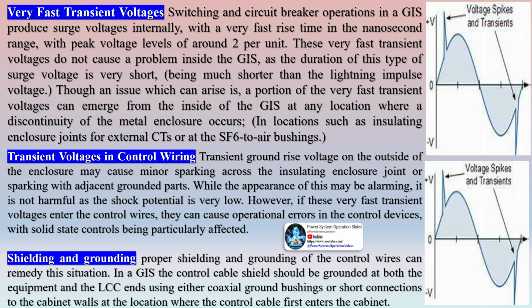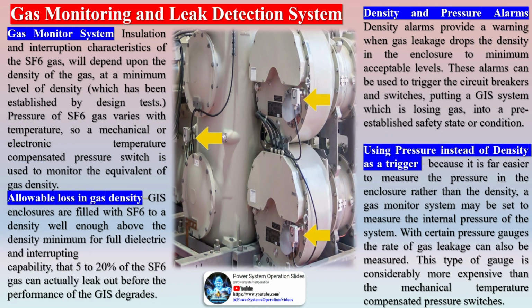These very fast transient voltages do not cause a problem inside the GIS, as the duration of this type of surge voltage is very short, being much shorter than the lightning impulse voltage. Though an issue which can arise is, a portion of the very fast transient voltages can emerge from the inside of the GIS at any location where a discontinuity of the metal enclosure occurs, in locations such as insulating enclosure joints for external CTs or at the SF6-to-air bushings.